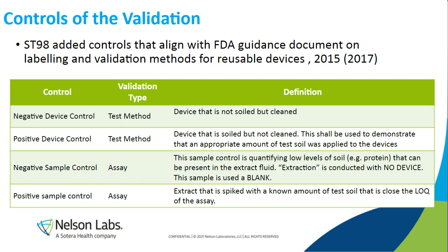So this control is in place to show that the test soil that you use can be picked up by any of your assays, and the amount of test soil is close to the LOQ of the assay. So you know that it was there, because what we're looking at is, after you've cleaned the devices, you will see your extract fluid. Can the assay pick up low levels or trace amounts of soil that's there? And that's what this control is actually establishing for you. So very important controls to have in a validation process, and historically they have been used, but not to the point where it was something that all test labs did. But it was something that was in the FDA guidance for a while.